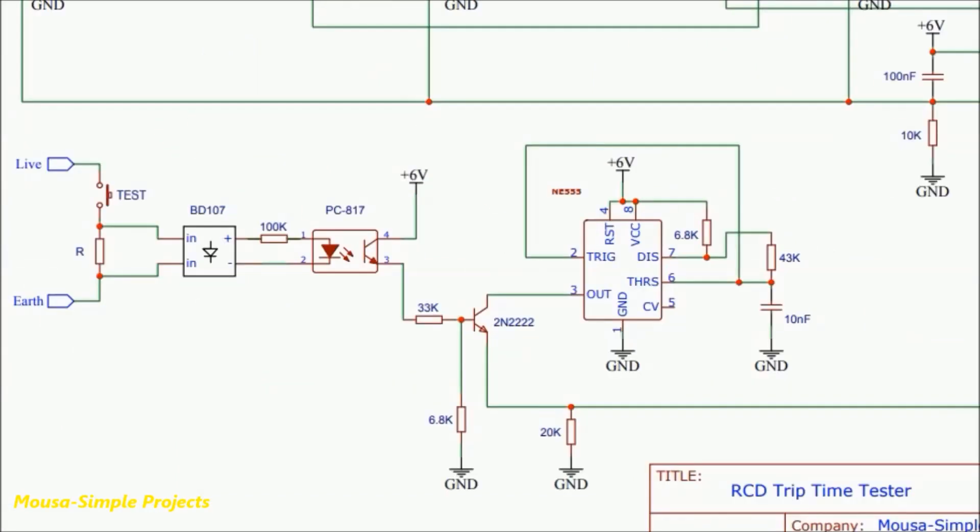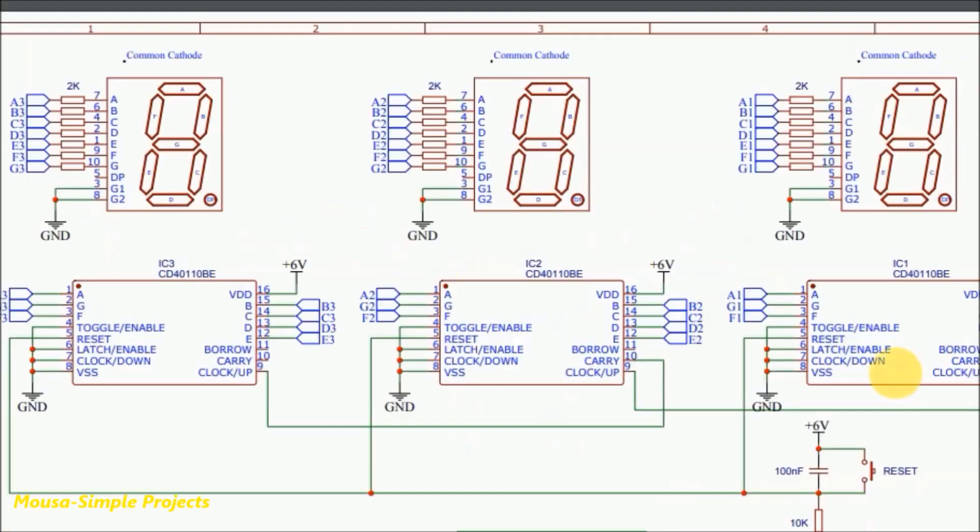But it stops counting when the RCD trips, because there is no more voltage across this resistor to keep the transistor on. So this 7-segment display shows you how long the RCD takes to react to any leakage current.